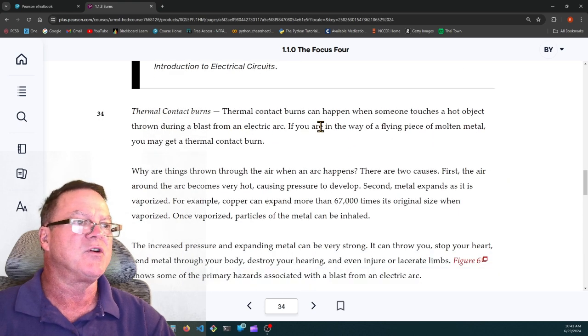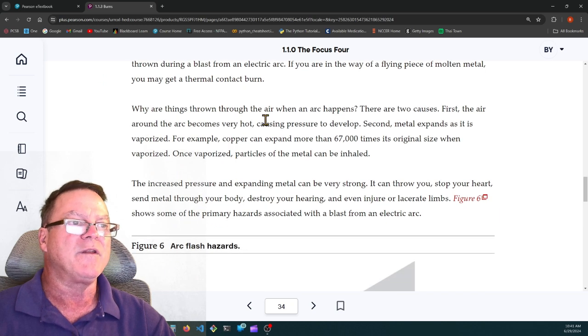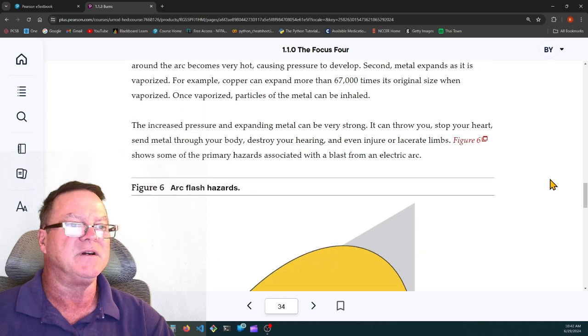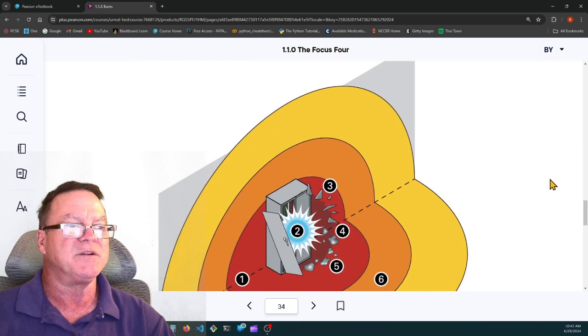Thermal contact burns. Thermal contact burns can happen when someone touches a hot object thrown during a blast from an electric arc. If you're in the way of a flying piece of molten metal, you may get a thermal contact burn. Why are things thrown through the air when an arc happens? There are two causes. First, the air around the arc becomes very hot, causing pressure to develop. Second, metal expands as it is vaporized. For example, copper can expand more than 67,000 times its original size when vaporized. Once vaporized, particles in the metal can be inhaled. That's a very bad situation to be in.